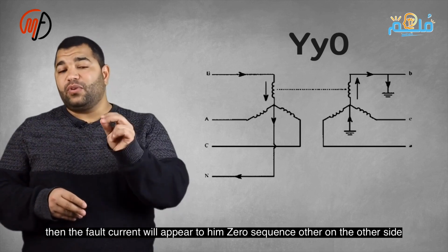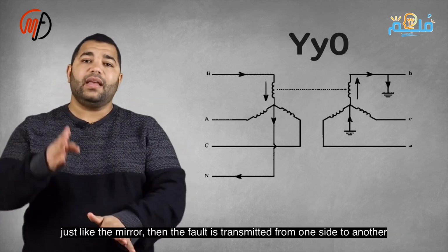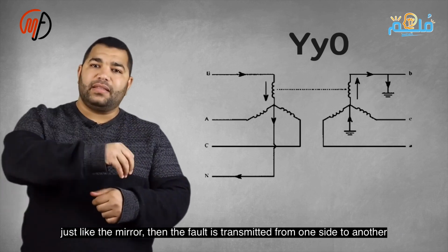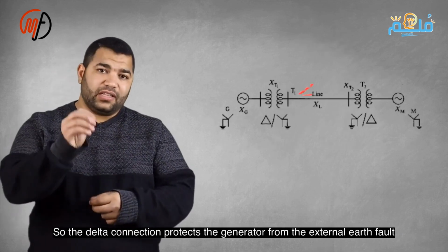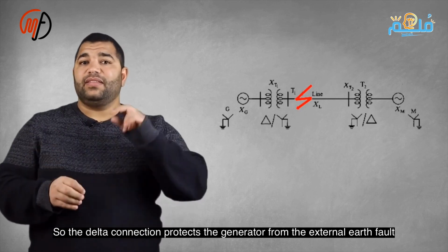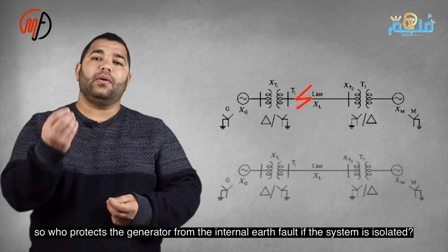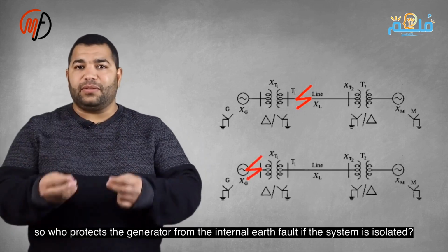So the fault current will show a zero sequence on the other side just like a mirror. The fault transfers from one side to the other. Therefore, the delta connection has protected the generator from external ground faults. But who protects the generator from internal ground faults if the system is isolated?